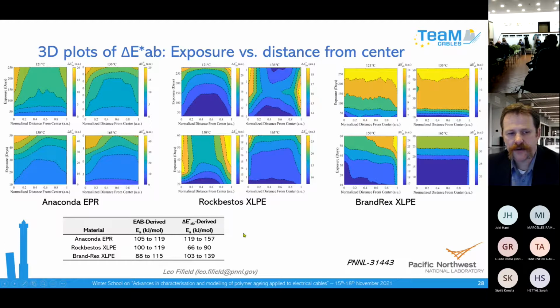One of the goals here, which worked reasonably well, was to compare normal activation energy. The normal process for calculating activation energy is often done with tensile elongation at break, and we compared that with the activation energy you might calculate by looking at just the interior of the cable material. If this DLO artifact of accelerated aging is really throwing off your lifetime prediction, then you might be able to see that by predicting the life from the interior of the cable versus the exterior of the cable.